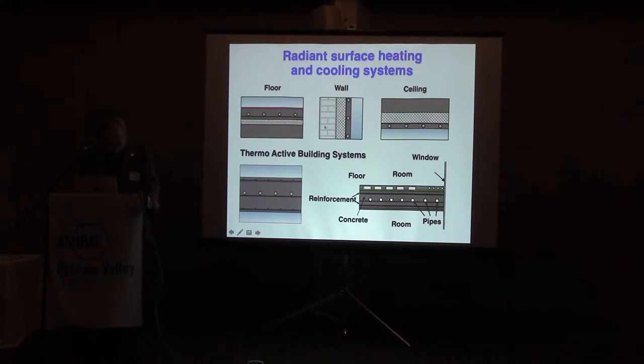And then we have a system which has grown in application since we did really the first one at the end of the 90s. And that is in the main construction slabs. In multi-story buildings, you integrate piping in the middle of the slab or inside the concrete between the upper and lower reinforcement. And why do we do that? That's because you want to use this slab as a storage. And the advantage with having a storage is that you can reduce peak load and you may transfer some of the needs for removing or supplying energy from daytime to nighttime. Especially it is relevant for cooling. So we see very much for buildings who want to have some cooling and don't want to have a full air conditioning, they apply this type of system. And I'll come back to how that will work.